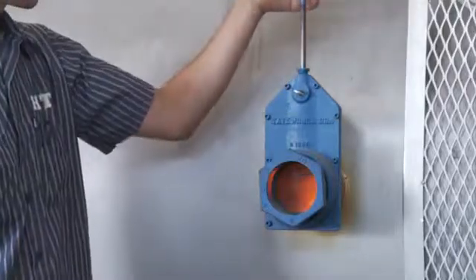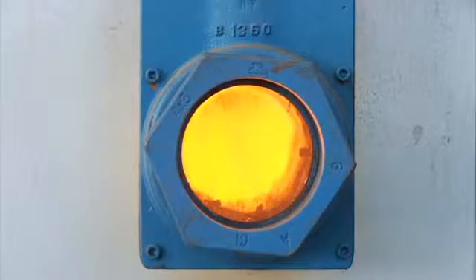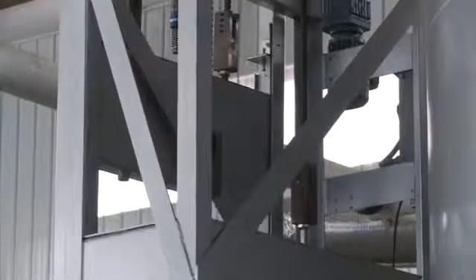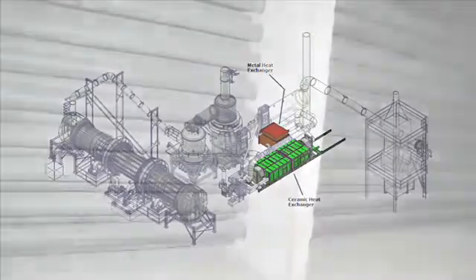In the full-scale system, the air is mixed in a very controlled environment with the syngas in the oxidizer. When the combustible syngas is mixed with oxygen in the air, it causes the gas to glow and heat to 2000 degrees Fahrenheit. When the gas in the oxidizer reaches 2000 degrees, the valve leaving the oxidizer is closed, diverting energy to the ceramic heat exchanger.